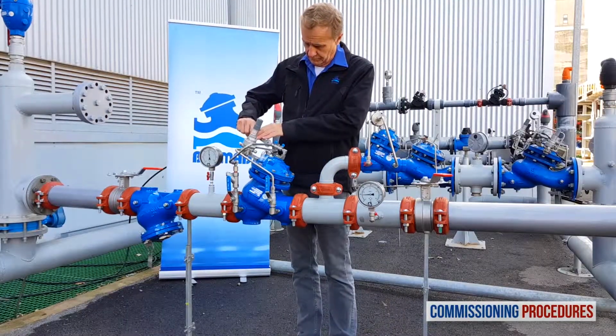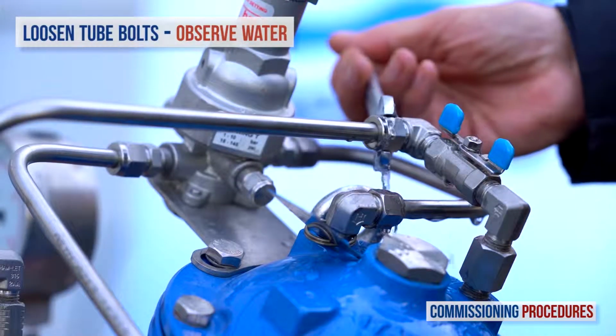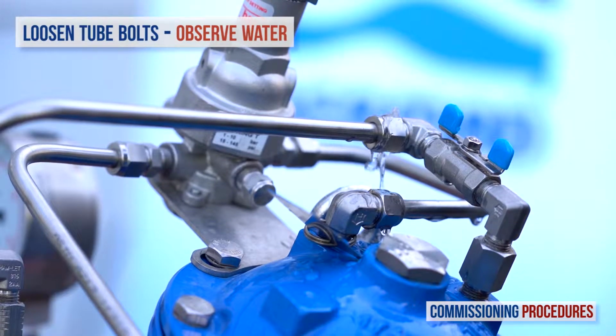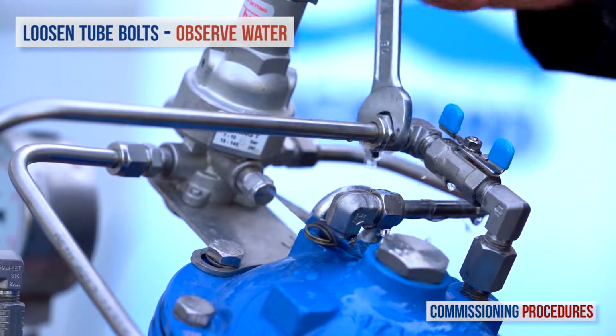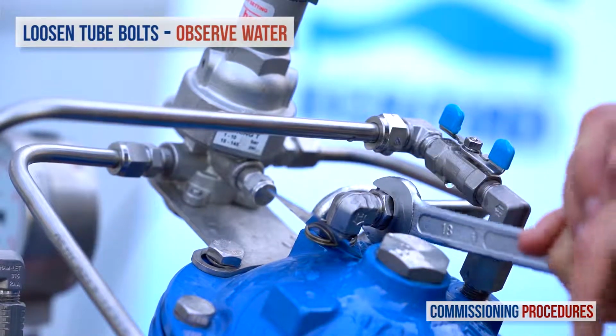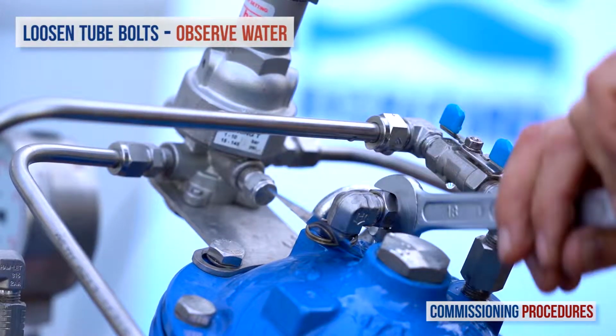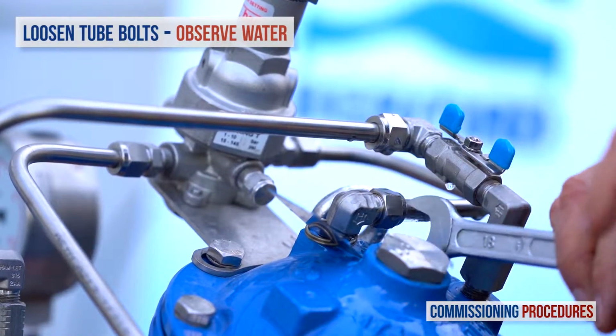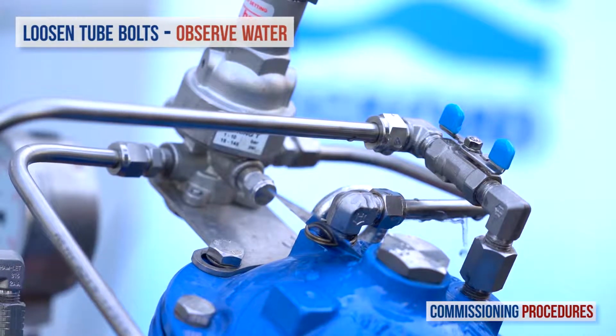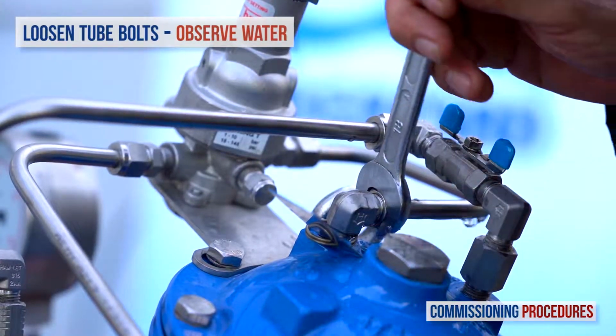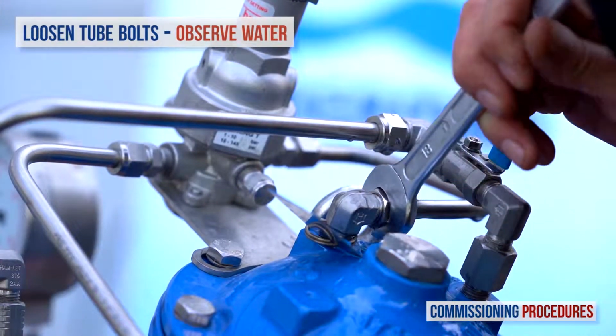To vent air from the valve's control loop, loosen the tube eye bolt attached to the valve cover at the highest point of the valve's control chamber. You may notice air exiting the eye bolt. As soon as you get a flow of water without air, retighten the tube fitting eye bolt.